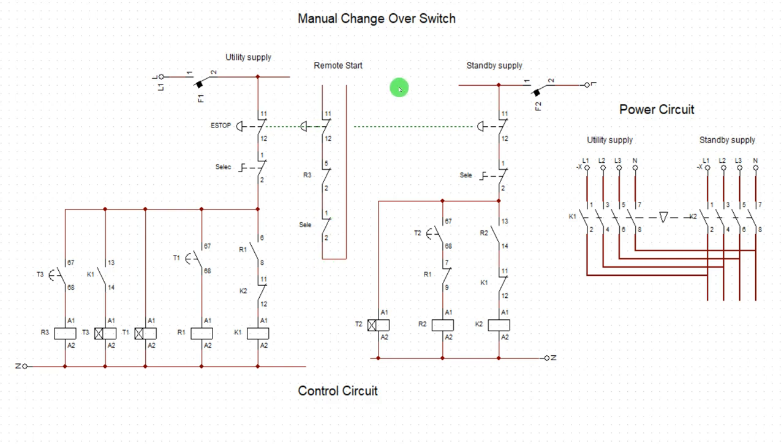All right. Now, if you go to any of the generator panel and you discover that the end user said once you press stop button, although before you design, you must go for inspection. When you get to inspection, you start the genset, you stop it, and now find your remote start. Whenever you get a proposal, you must go for inspection, check the length of cable from where the ATS is going to be situated to the powerhouse, anywhere you want to locate it. Now, this is an inspection you carry out. Now, find out the remote start, the start time, so that you know the component to integrate in your ATS.